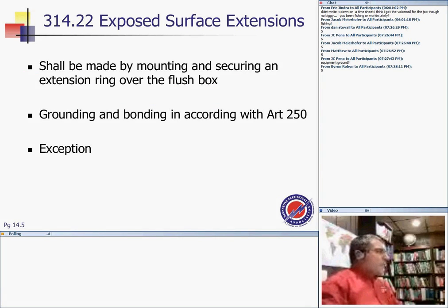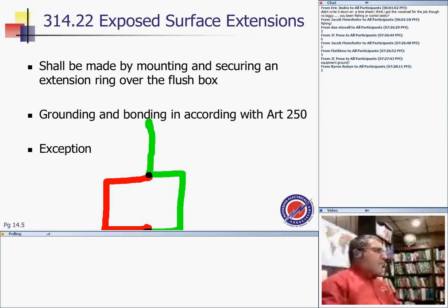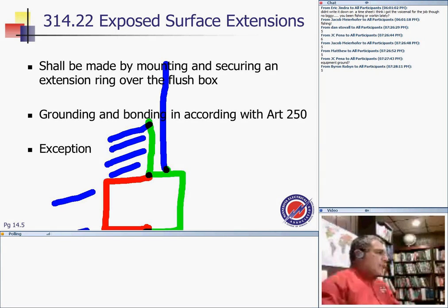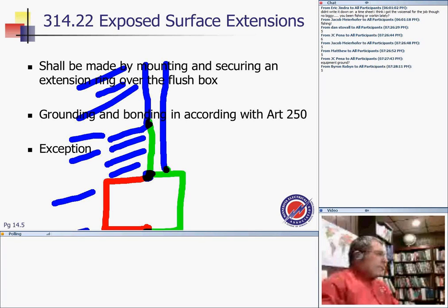Surfaces extending shall be made by mounting and securing an extension ring or flush cover. I don't know how many of you have seen a box in the wall that you extend. So you have the box here, and this is the wall. You extend the box, and from here I attach a conduit that runs inside the wall all the way up to here. If you have to extend it, guys, you have to maintain the integrity of the grounding system by attaching it properly and bonding it. How many have installed an extension of a box, for whatever reason?